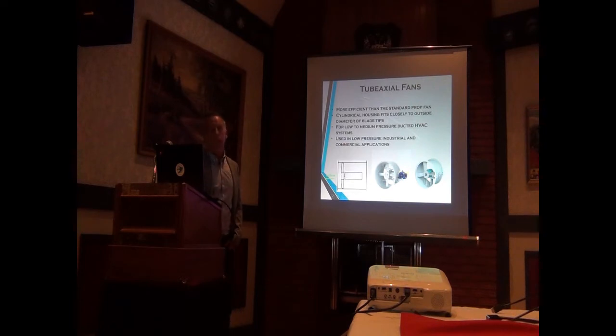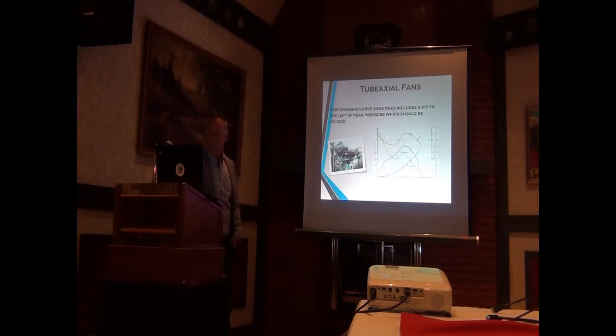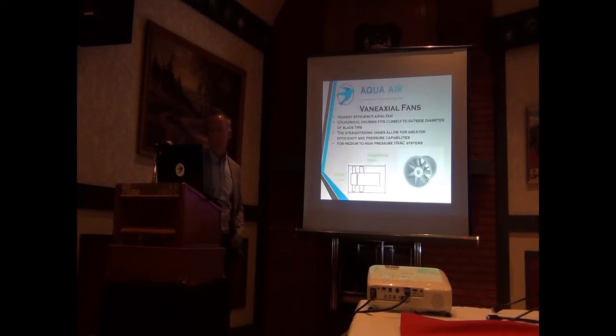Often you'll see these fans tucked up in a mechanical room up high in a round duct, moving maybe exhaust air or return air. Tube axial fans, much like the forward curve fans, can overload, so again you have to be accurate on your selection. You want to make sure you stay on the right hand side of the curve. If you get over the other side of the curve, the overspeeding, that running downhill, can't stop the fan. They're not super efficient, but they're an effective way to move large volumes at low static pressure.